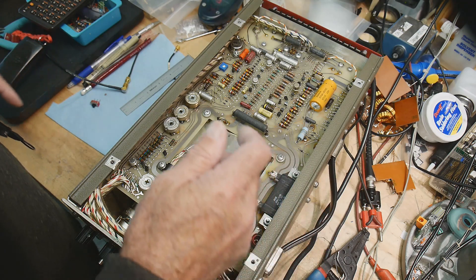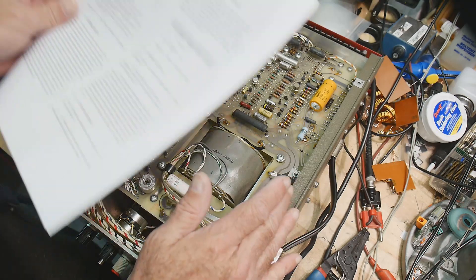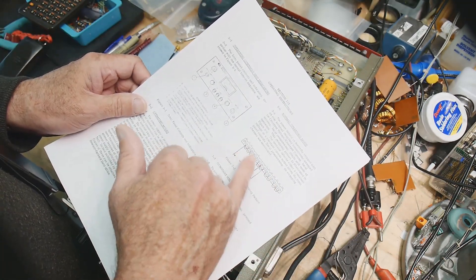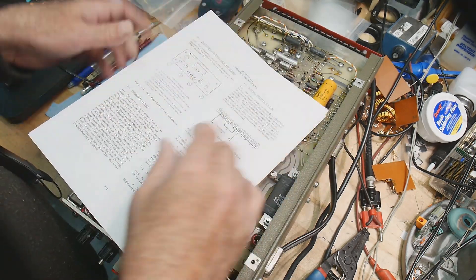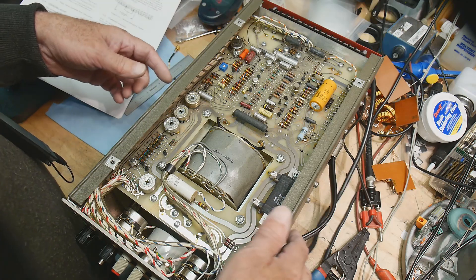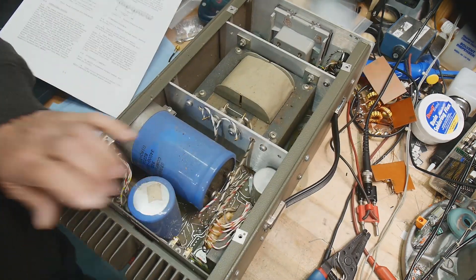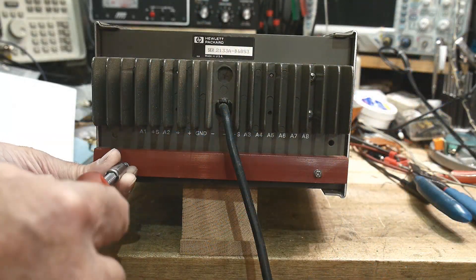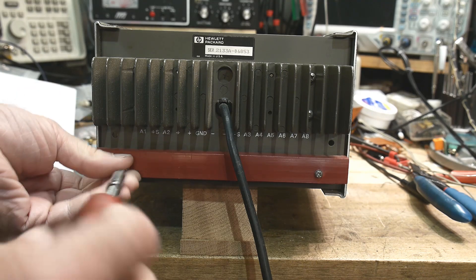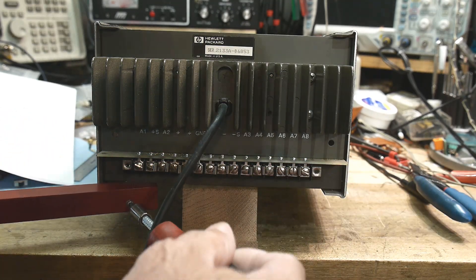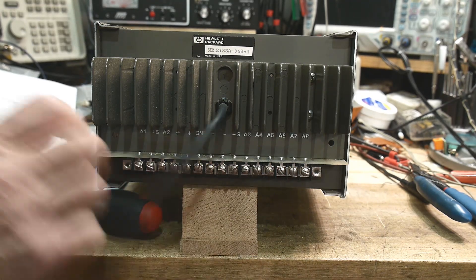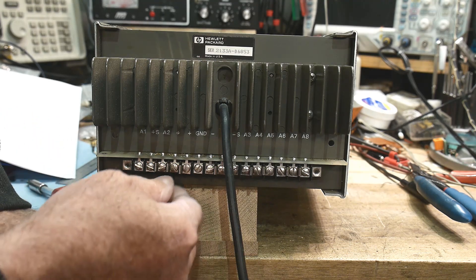Let's take a look at the back. Make sure it's strapped right. A lot of times these things come out of racks and they have remote sensing. You're able to bring the sense leads on separate wires out to the device and take into account any cable losses. It's kind of like a Kelvin contact. We need to make sure it's strapped right for our use.